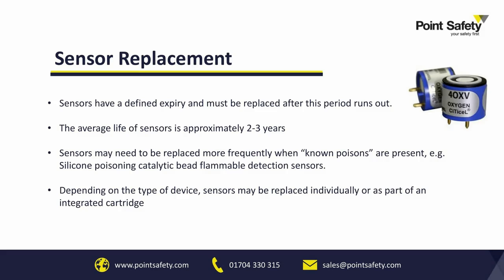Again, the importance of calibration and bump testing is that, especially on the catalytic bead or pellistor sensors, they are liable to get affected by poisoning, especially from silicones within the atmosphere. These create a glass film over the catalytic bead within the sensor and stop the gas being absorbed. So it's important to be testing and bump testing these regularly to know if that has happened, and your detector is no longer providing the protection you require.